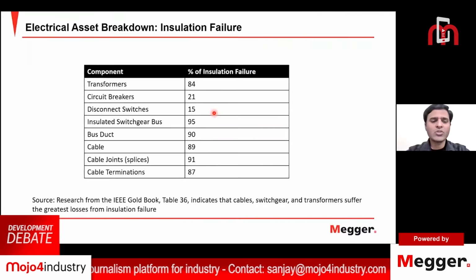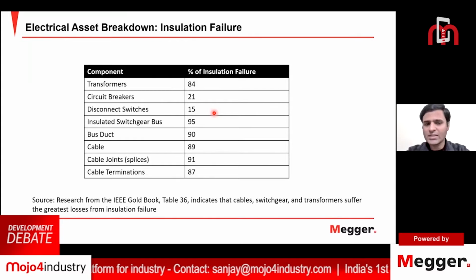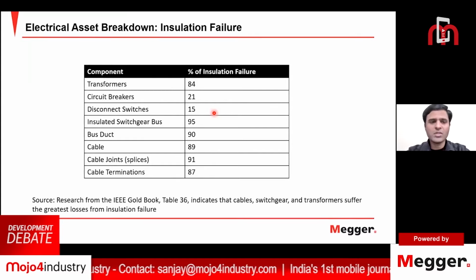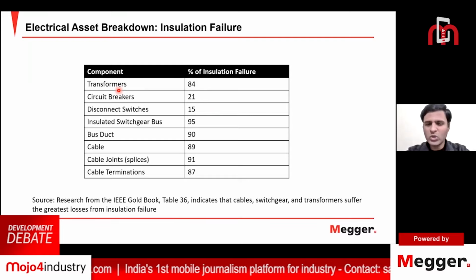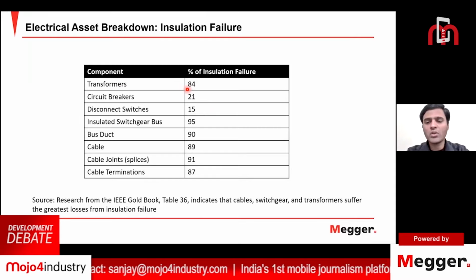So moving forward, IEEE Gold Book Table 36 states that the electrical assets, say transformer, circuit breaker, or cables, etc., all types of electrical assets face a failure majorly due to an insulation failure in their electrical assets. The table tells in detail that 84% of the failures in the transformers are due to the insulation failures. Transformer, as you all are aware, the transformers are the heart of the substation. So to maintain a good healthiness of the transformer, we should have a good strategic plan to do maintenance on a timely basis, on a condition based basis.